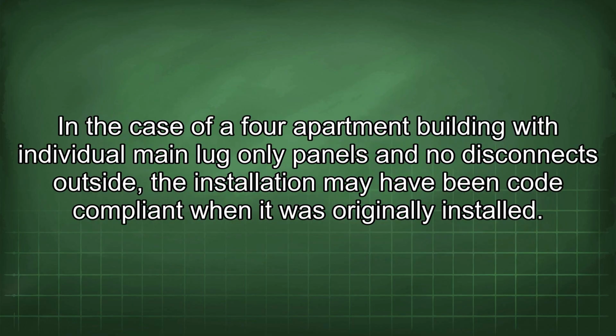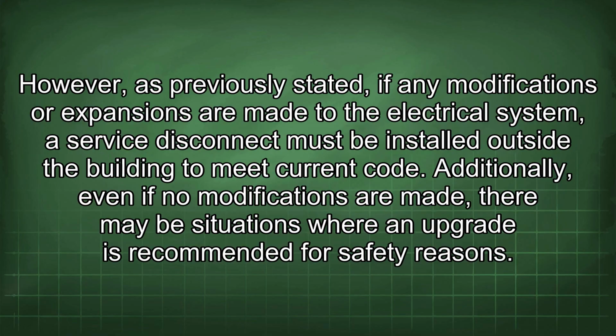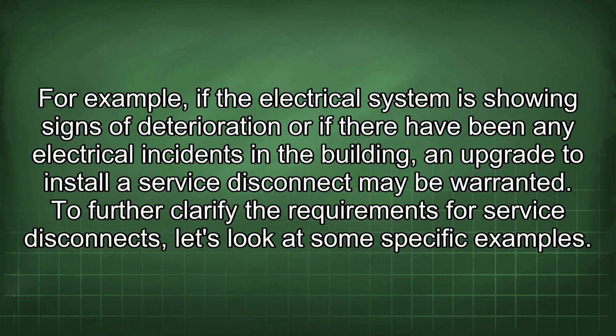In the case of a 4-apartment building with individual main lug only panels and no disconnects outside, the installation may have been code compliant when it was originally installed. However, as previously stated, if any modifications or expansions are made to the electrical system, a service disconnect must be installed outside the building to meet current code. Additionally, even if no modifications are made, there may be situations where an upgrade is recommended for safety reasons. For example, if the electrical system is showing signs of deterioration or if there have been any electrical incidents in the building, an upgrade to install a service disconnect may be warranted.